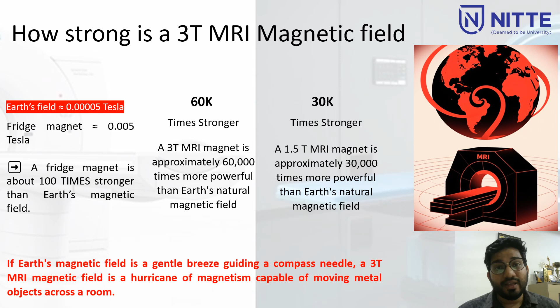It cannot be stopped, and can reach 50 to 100 kilometers per hour. So the strongest, which is strongest in a 3 Tesla MRI system. The static magnetic field, that is nothing but B0 in MRI, is always on, 24/7, even when no scan is happening. That we have to remember. It is not like CT or X-ray machines, which we can switch off. An MRI machine you are never switching off. It is on 24/7.